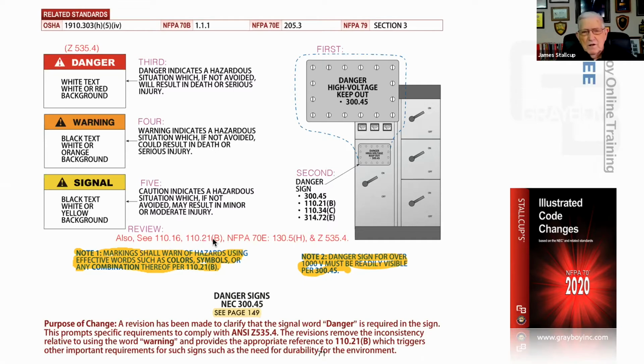Then 110.21(b) is your field identification label requirement, from 70E. Now the owner of the equipment has to put this on - the installer and engineering designer requires this. Then we go over to Z535 and get some information about what we might want to put on the label. If you have our 70E workbook, we give you a number of labels in there that could be used.